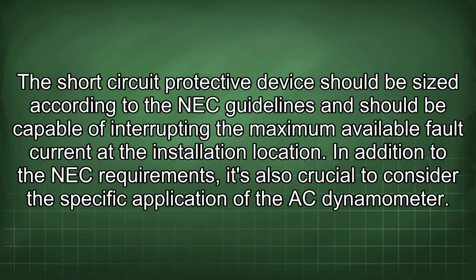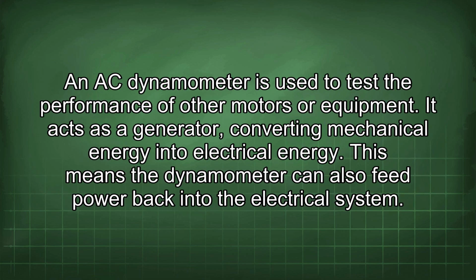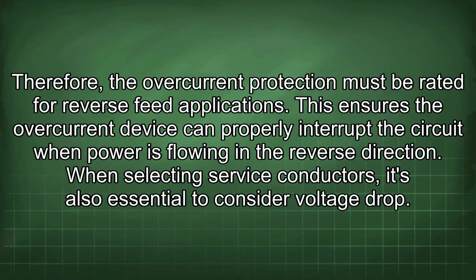In addition to the NEC requirements, it's also crucial to consider the specific application of the AC dynamometer. An AC dynamometer is used to test the performance of other motors or equipment. It acts as a generator, converting mechanical energy into electrical energy. This means the dynamometer can also feed power back into the electrical system. Therefore, the overcurrent protection must be rated for reverse feed applications. This ensures the overcurrent device can properly interrupt the circuit when power is flowing in the reverse direction.